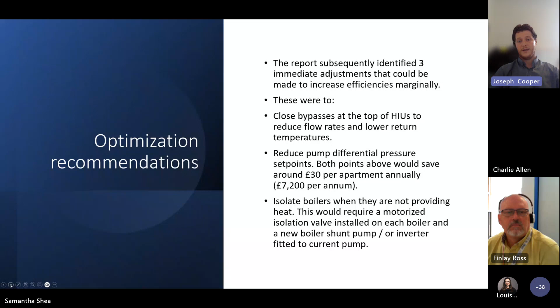It also recommended to isolate boilers when they're not providing heat, but this would require a motorised isolation valve installed on each boiler and a new boiler shunt pump or inverter fitted to the current pumps. The prominent recommendation was to replace all of the existing HIUs due to their poor condition, reliability and efficiency when providing heat within the apartments. The economic case to carry out this work was significantly strengthened by the installation of a water source heat pump and potentially achieving the capital funding through HNES in the future.